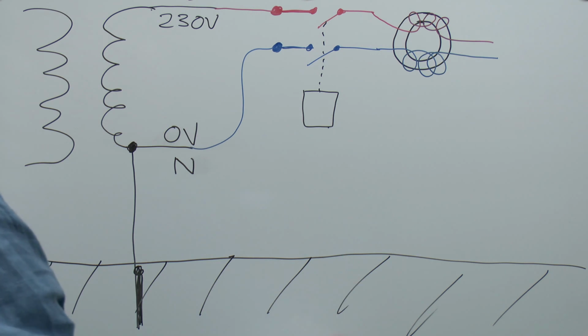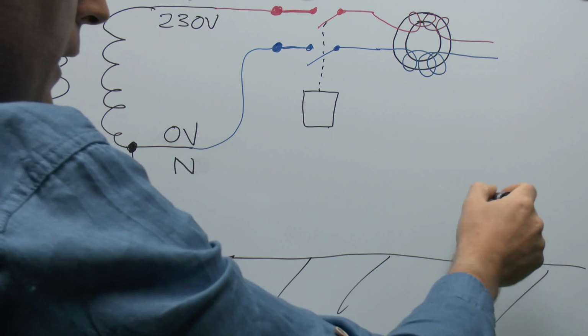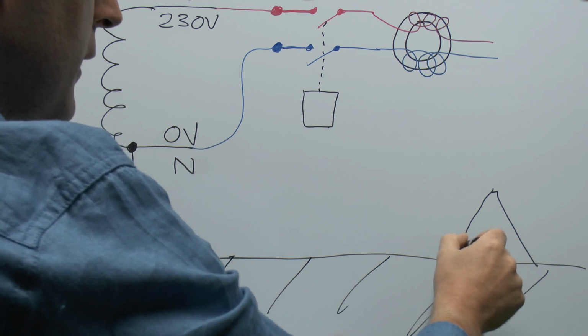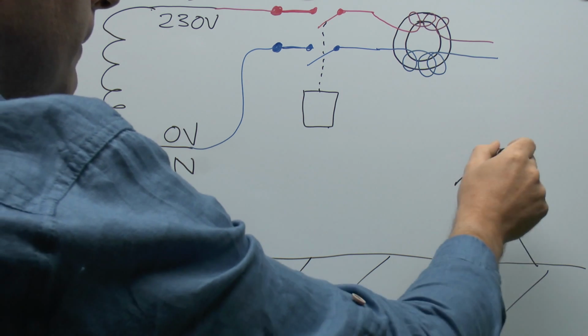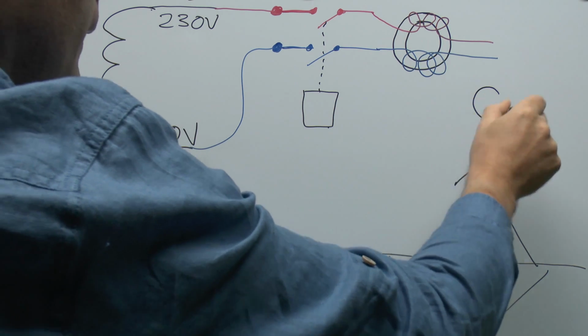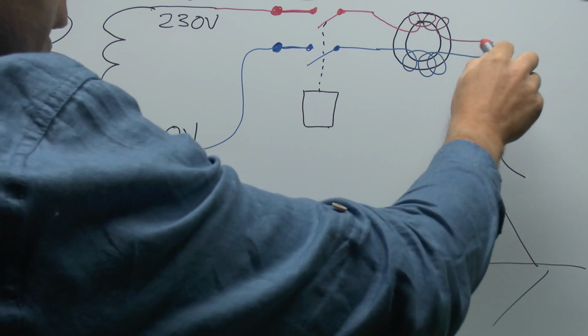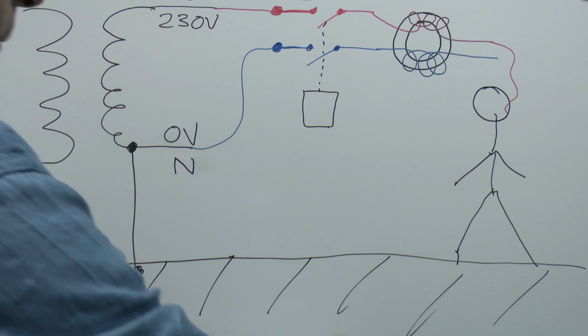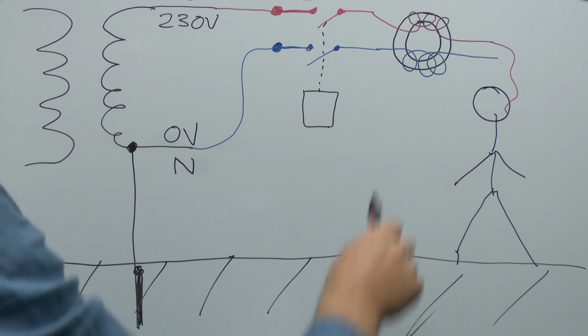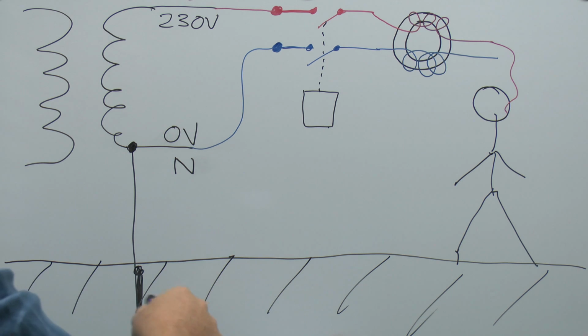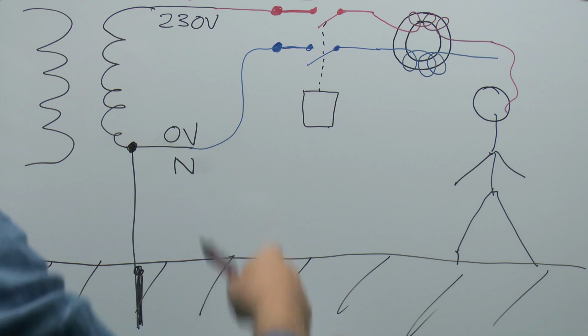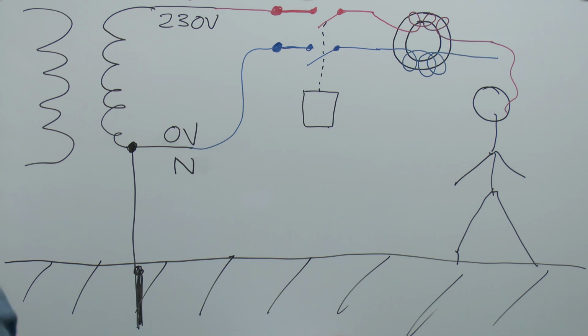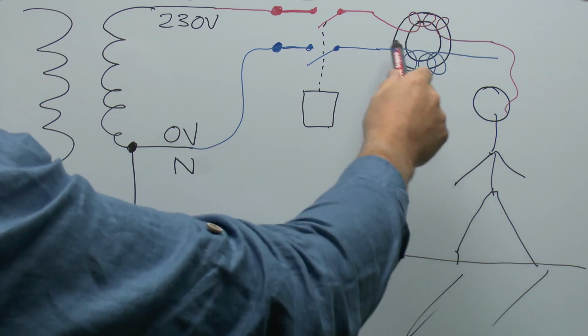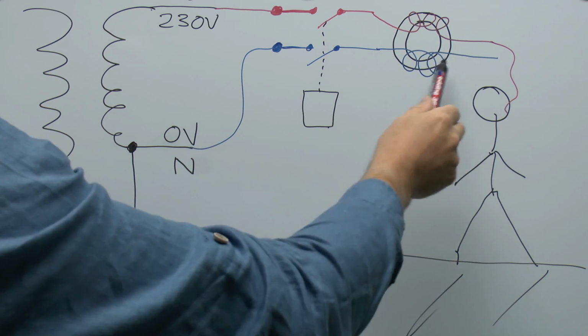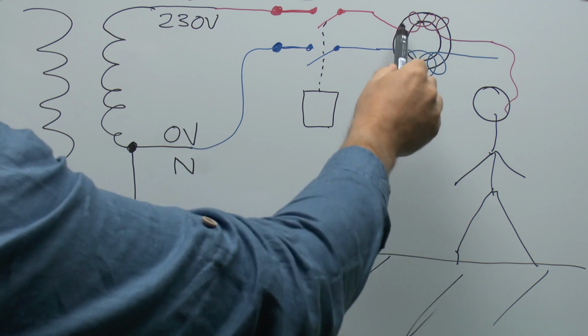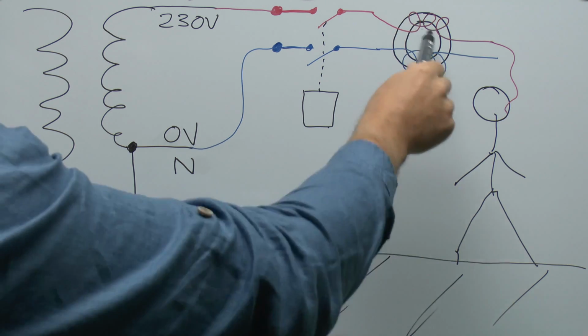Of course, when somebody touches the live wire, or there's some fault over here, so we put a person here standing on the ground. If somehow the live wire came into contact with the individual, some of the current will now flow via the path here back through the earth to the transformer, and obviously some will go via the neutral as it was intended. So you'll have an imbalance between the two currents, so generally the current going out would be greater than the current returning, and this will cause a magnetic field to be generated within the core.